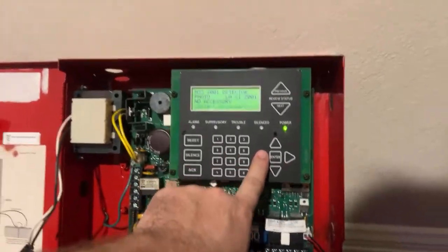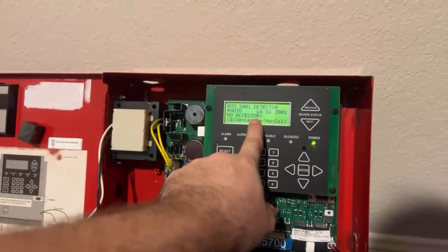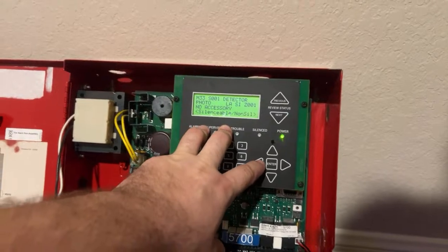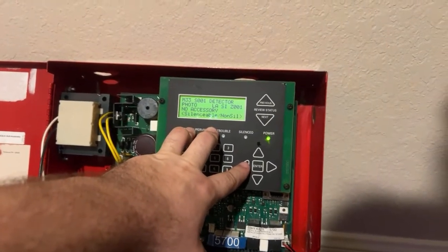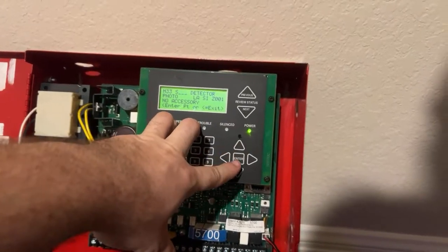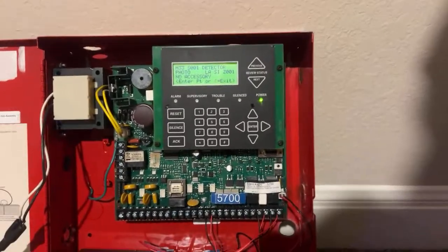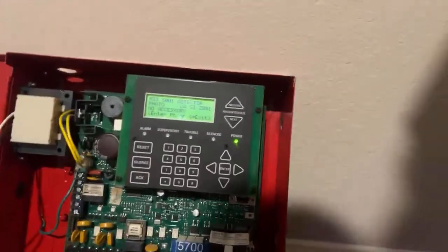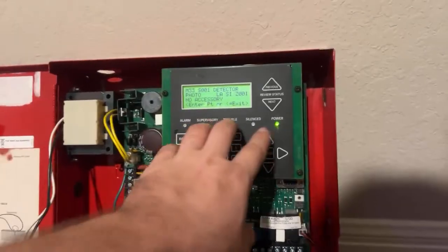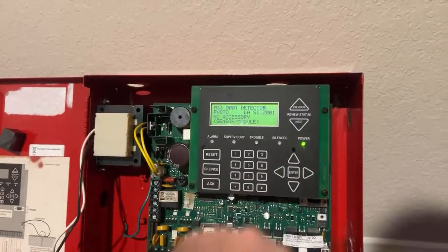And then basically just latching, silenceable. You can't change this one, the latching part. That's just how they work. You can make it silenceable or non-silenceable. We'll have it silenceable, but duct detectors, you do not want those to be silenceable, because you don't want to silence the panel and then the relay clicks and then the air conditioner starts right back up. So yeah, that's the only sensor that we have.